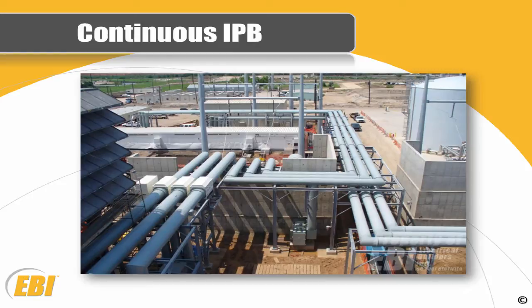This is a large, continuous IPB system. Everything is welded on the enclosures from one end to the other. Even where you have a generator breaker, the housing of the generator breaker itself is actually made out of aluminum, and it is continuous all the way through those also.